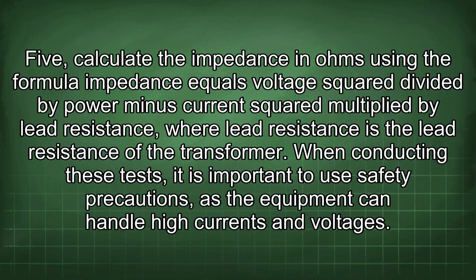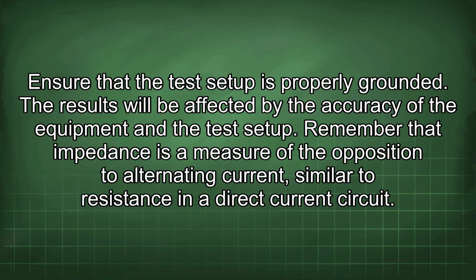When conducting these tests, it is important to use safety precautions, as the equipment can handle high currents and voltages. Ensure that the test setup is properly grounded. The results will be affected by the accuracy of the equipment and the test setup. Remember that impedance is a measure of the opposition to alternating current, similar to resistance in a direct current circuit.